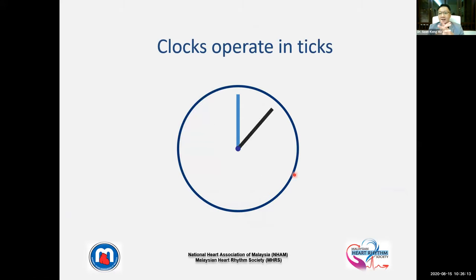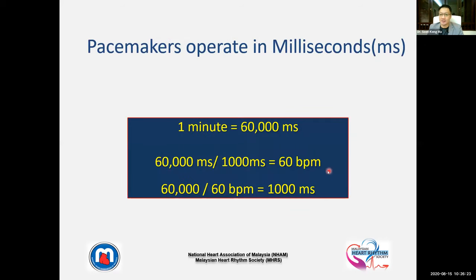Now, analogous to a clock which operates in ticks, a pacemaker operates in milliseconds, also ticks, but very fast. Now this formula, as a pacemaker fundamental learner, we need to understand: 1 minute equals 60,000 milliseconds. So if you want to talk in the language of pacemaker, you need to talk not in beats per minute, but in milliseconds. How to convert that? Easy, take 60,000 and divide it by the number of beats per minute, and then you get the milliseconds that you want.